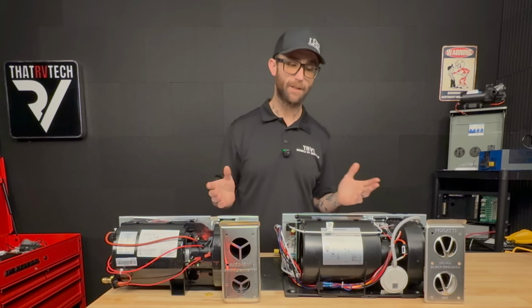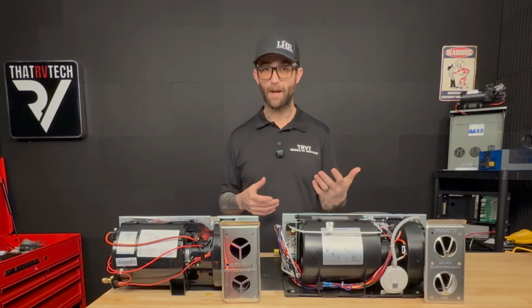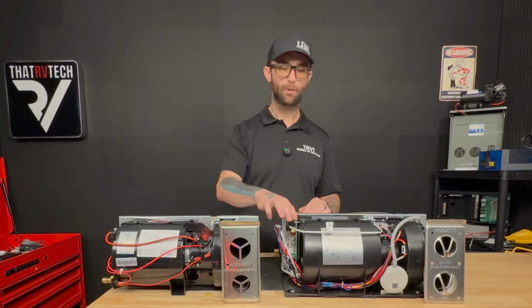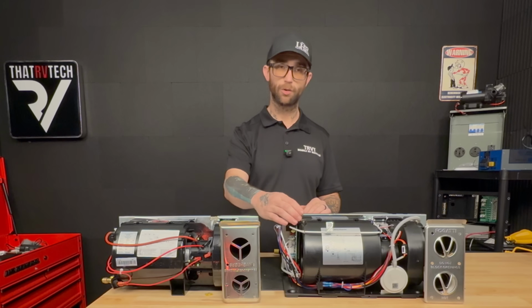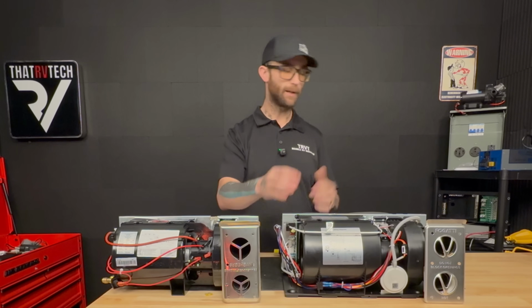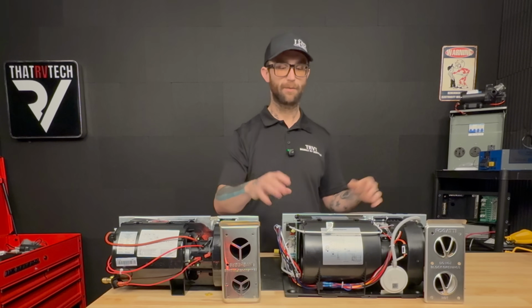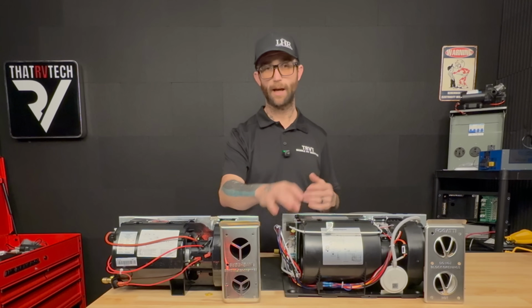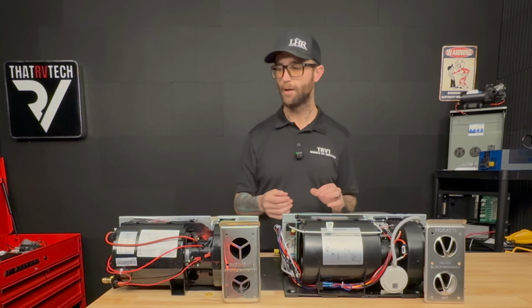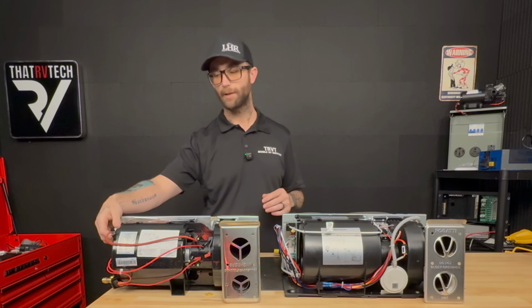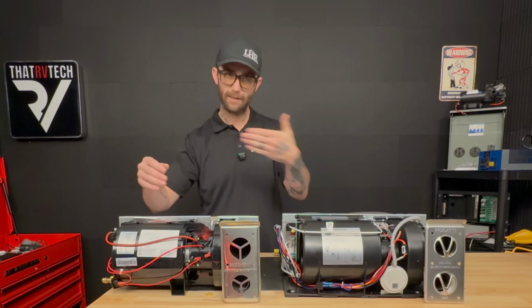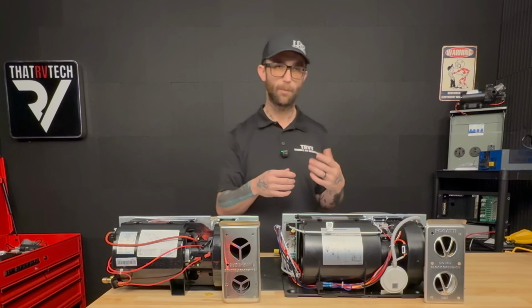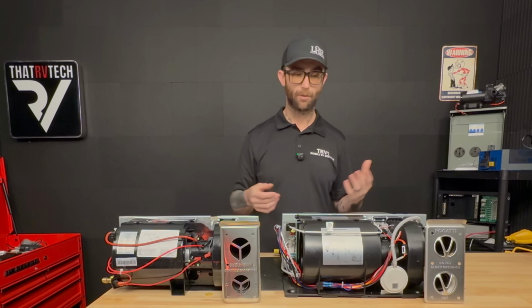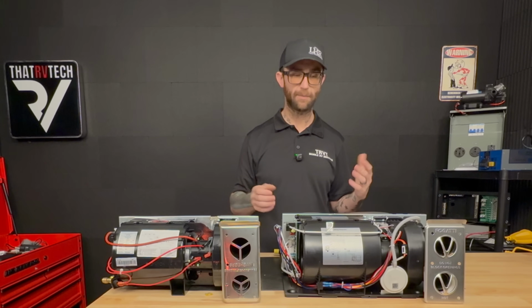But again, back to serviceability, the only con I found is the control board on this one is actually physically screwed to the blower motor housing. So you'd have to have that whole cover off just to get this control board out and say put a test board in to try it. Whereas on the Suburban, it's actually a pro, because I can slide my hand in there, disconnect it, pull the board out, throw a test board in, or replace the board easy peasy.